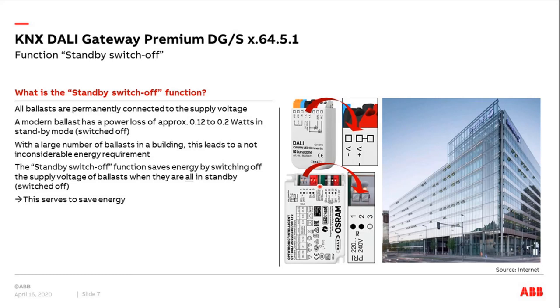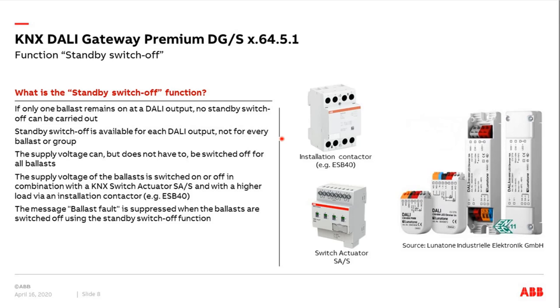This is sometimes a requirement for different kinds of LEED certificates or other energy-saving certifications. The standby switch-off function is only possible if all DALI devices on one output are switched off — this is very important. When we switch off the DALI supply voltage, the gateway does not send a ballast failure into the KNX world. This function can only work per complete output; it is not possible to use only some groups.